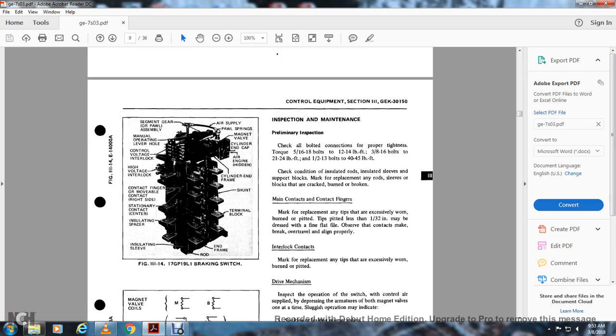Inspection and maintenance. Preliminary inspection. Check all the bolts and connect with the proper type with the torque: the 5/16 inch, 18 thread bolt with 12 foot-pounds, a 3/8 inch, 16 thread bolt to 21 to 24 foot-pounds, a 1/2 inch, 13 thread bolt with 40 to 45 pounds of torque.